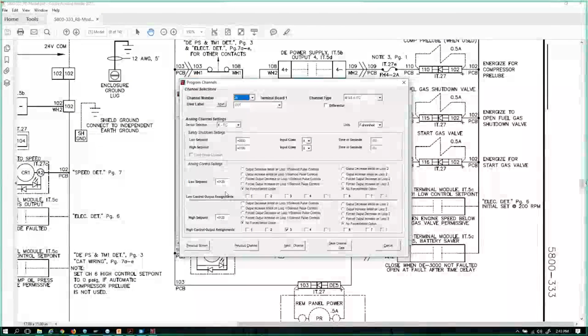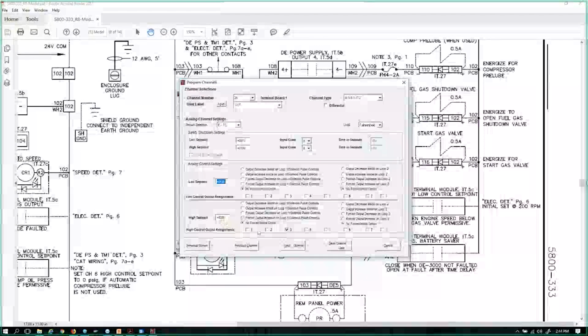A lot of people are going to say, well, wait a minute, why is it a low control set point? Well, think of the low control set point, for the purposes of what we were just looking at for the analog speed control, as a second high control set point. The reason we do that is in some cases somebody might say, let's use 80 degrees Fahrenheit down here on the low, high control set point, which is going to be just like what it says. So if the oil temperature is equal to or greater than 80, it's going to turn on this digital output 3. What might I be using that for?